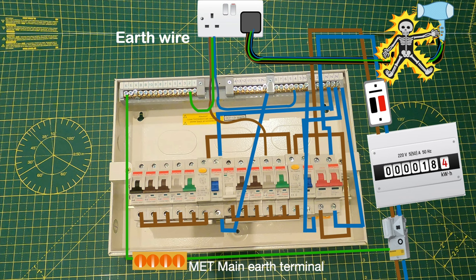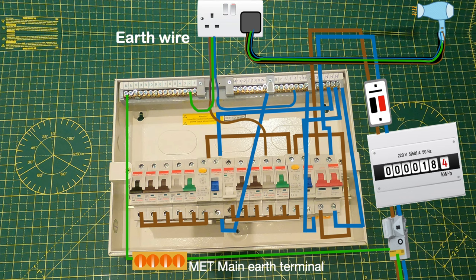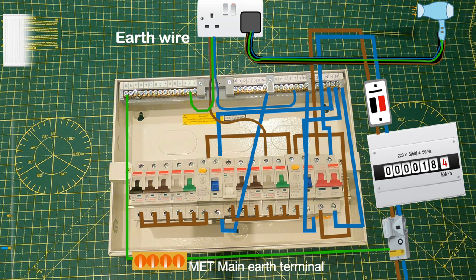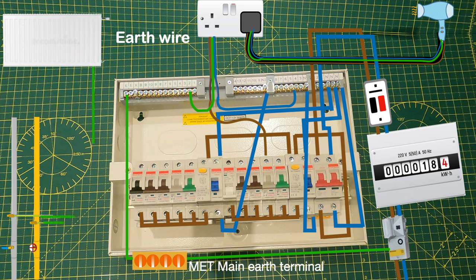Let's take a look at the path the current should take should there be a fault on the appliance. The current flows from the appliance back to the socket, then from the socket to the earth terminal bar inside the consumer unit, which makes its way back to the main earth terminal bar and back to the main cutout fuse and out of the property. You will have many earth wires going out to all the different circuits within your home, and you also have other earthing wires connecting from the main earthing terminal such as metal pipes from the plumbing, gas pipes, and any other extraneous metal surfaces. That way if there's any kind of electrical fault, the current will flow through the earth wire to ground, tripping the RCD almost immediately and preventing anyone from getting an electric shock.